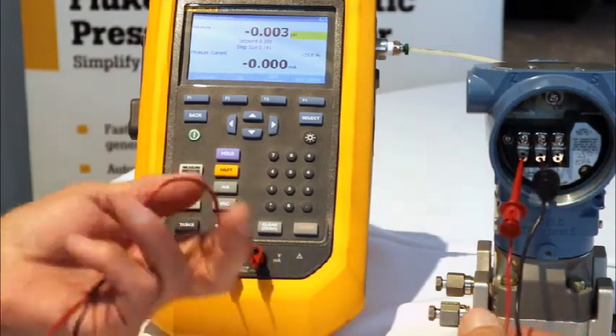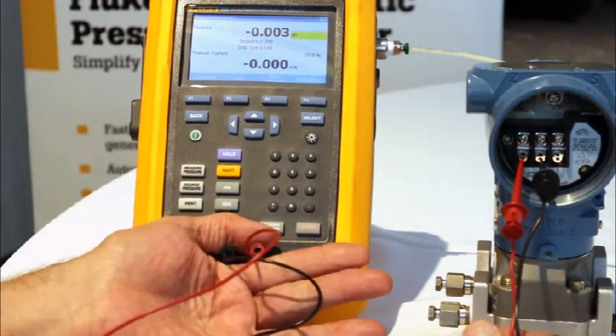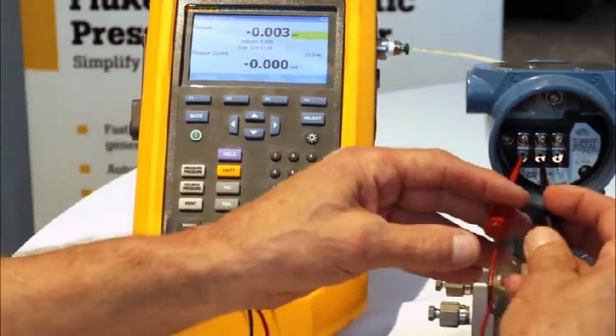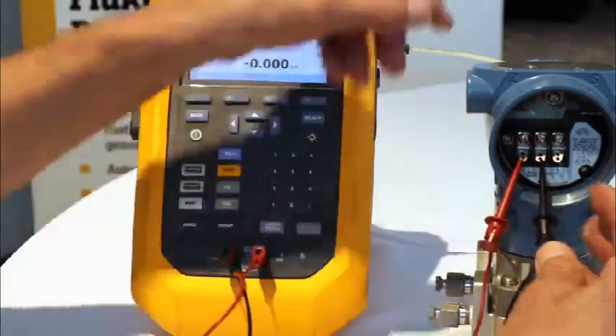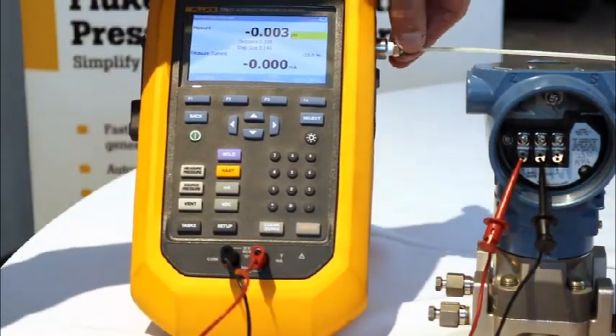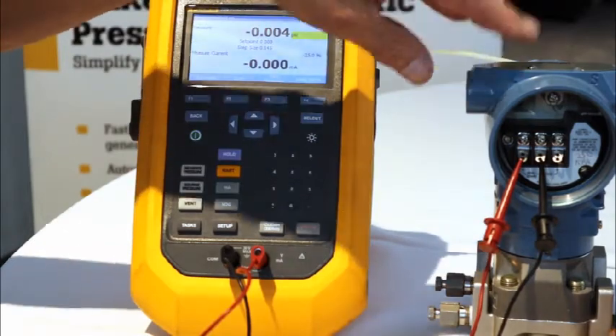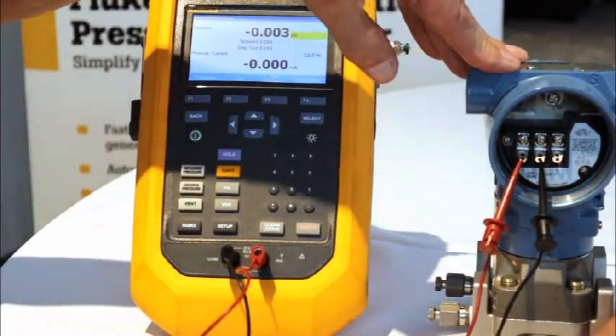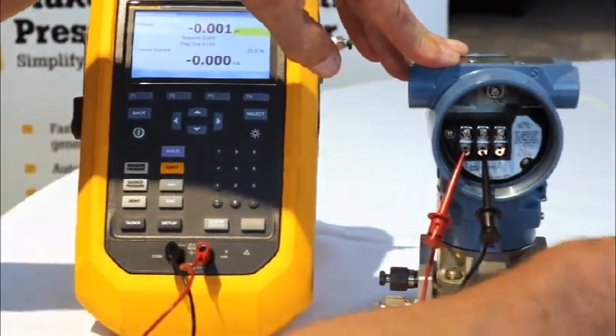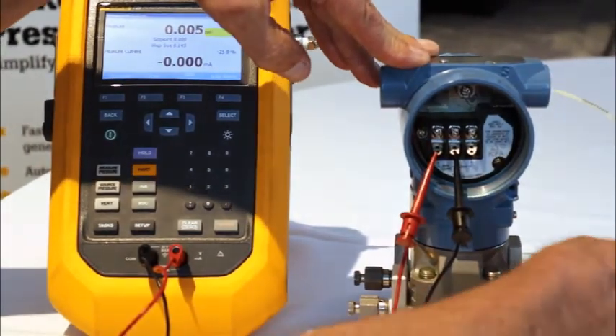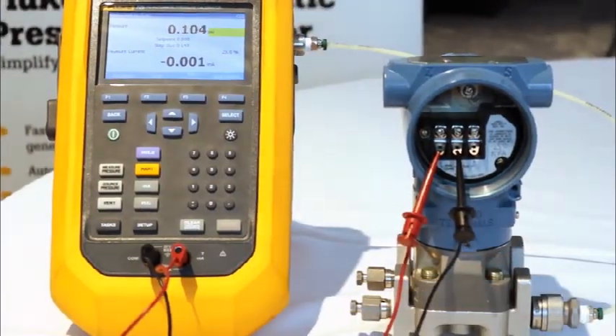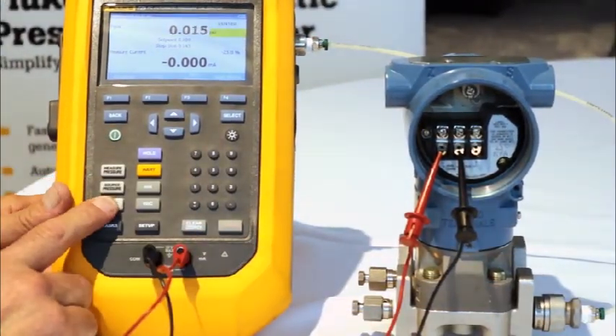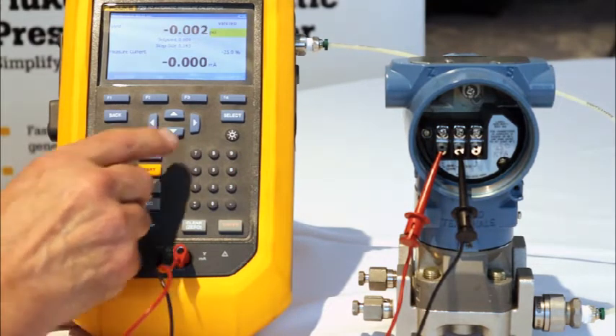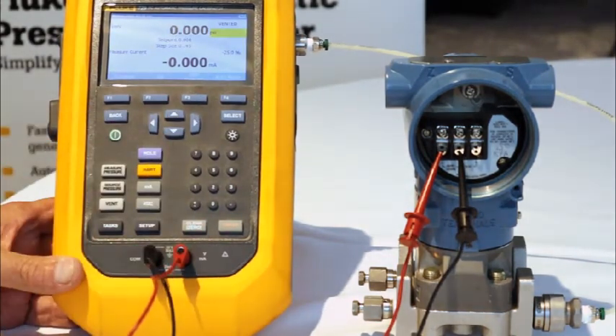So we're all connected up here. I've got the milliamp measurement jacks in the 729 connected to the power terminals on the 3051, and I've got a pressure hose going from the output of the Automatic Pressure Calibrator into the input of the Rosemount 3051. Make sure I've got a nice tight connection here. There we go. Now the first thing I want to do is vent the calibrator to atmosphere, ensure I have a good zero, so zero it out.